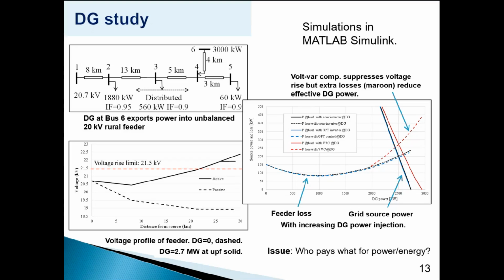The issue then becomes, who should be paying for the excess losses that occur when a renewable energy generator invokes volt-var compensation? The customers aren't getting the energy, but the DG is pushing it out into the system. It just warms up the wires in the atmosphere, and somebody has to pay somewhere.